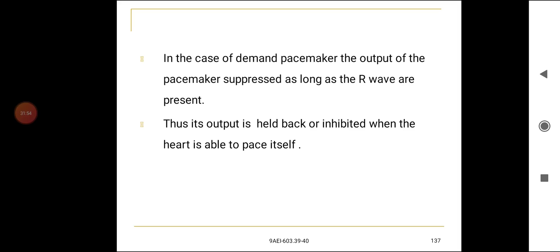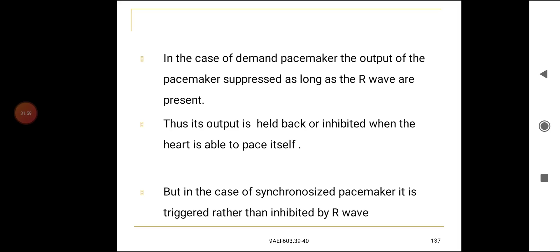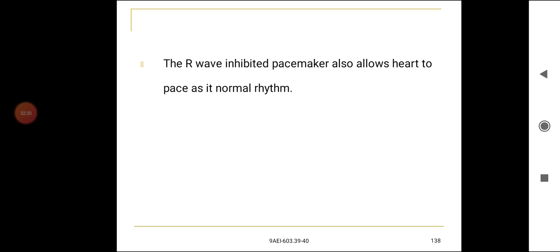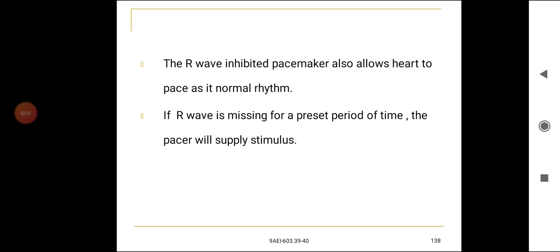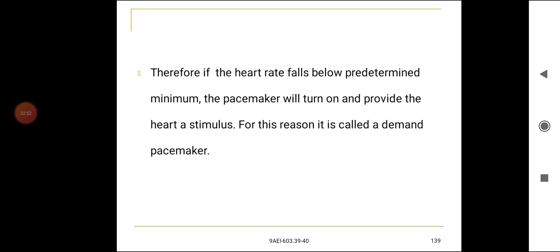Thus, its output is held back or inhibited when the heart is able to beat by itself. But in the case of synchronized pacemaker, it is triggered rather than inhibited by R wave. The R wave inhibited pacemaker also allows the heart to pace at its normal rhythm. If R wave is missing for a preset period of time, the pacemaker will supply a stimulus. Therefore, if the heart rate falls below a predetermined minimum, the pacemaker is turned on and provides the heart a stimulus. For this reason, it is called a demand pacemaker.